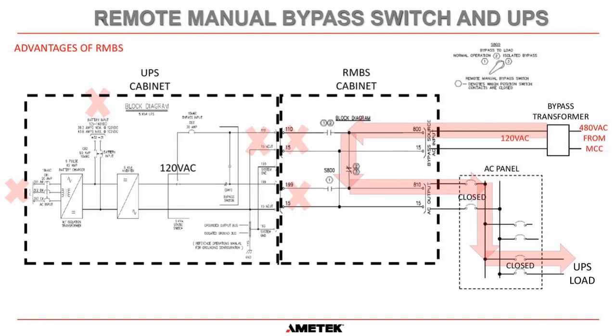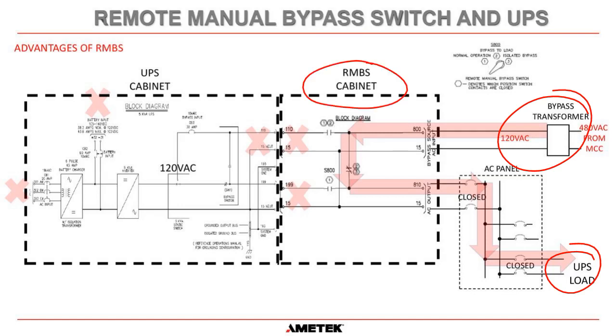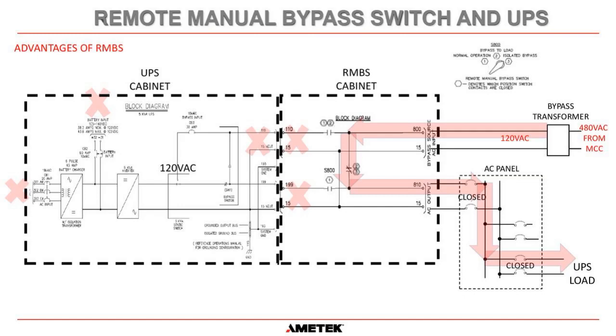And the last thing I want to touch on is, well, a lot of people say, well, when you're on bypass, you don't have any battery backup. So yes, we can keep these UPS loads powered, but we're kind of in a bad situation where if we have a power failure in the plant during the installation of this RMBS cabinet, then we could have a power outage to our UPS loads. Well, there's a way to get around that.